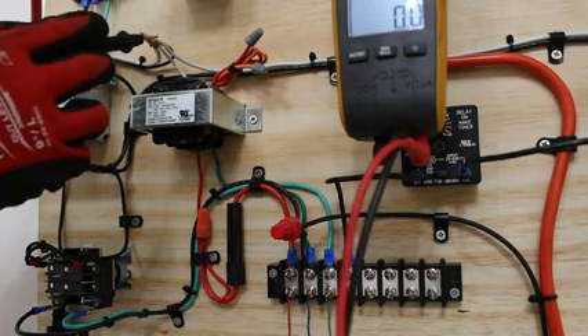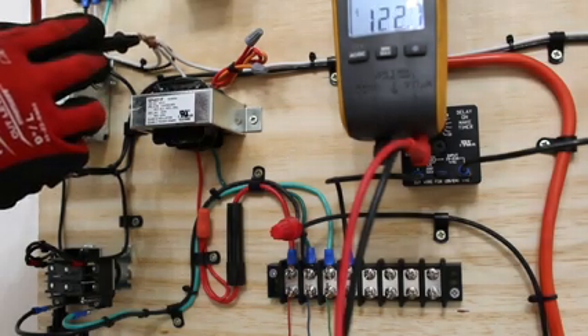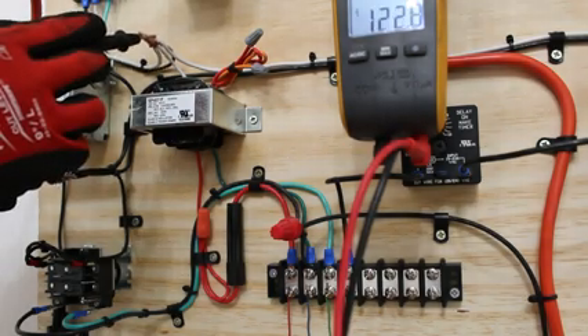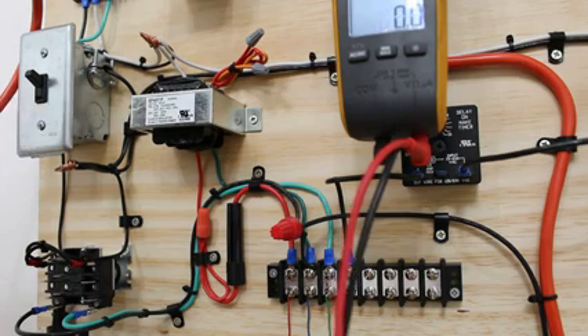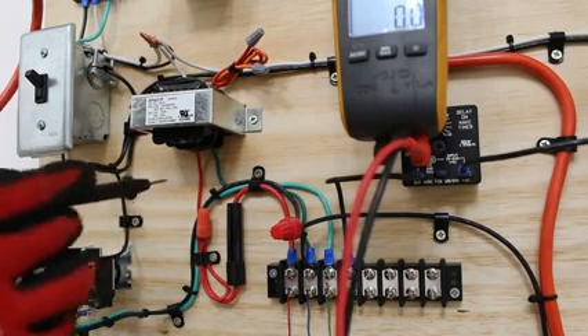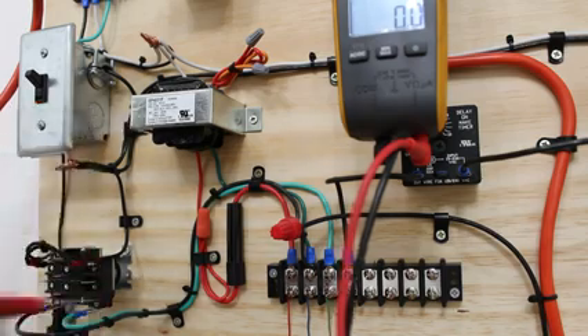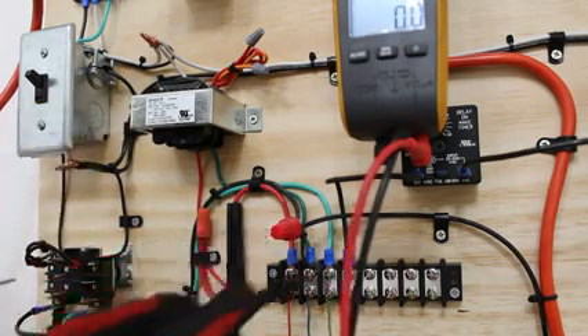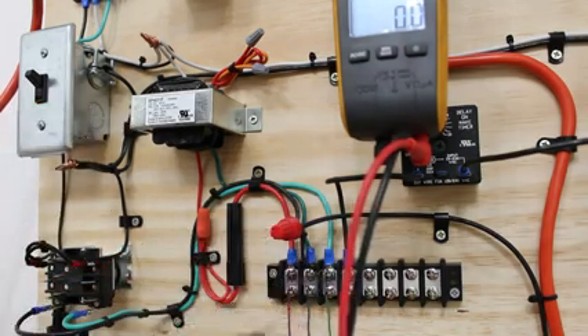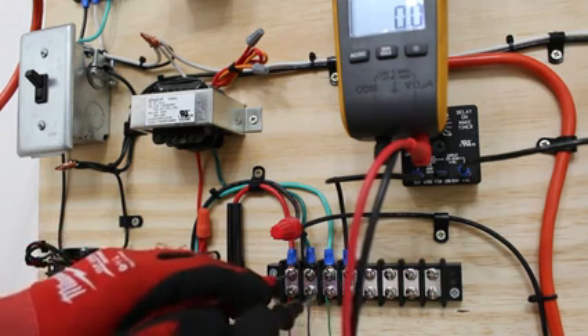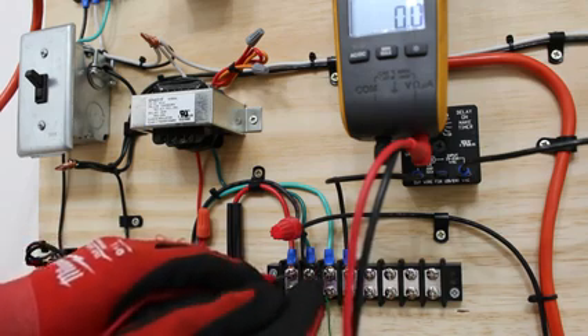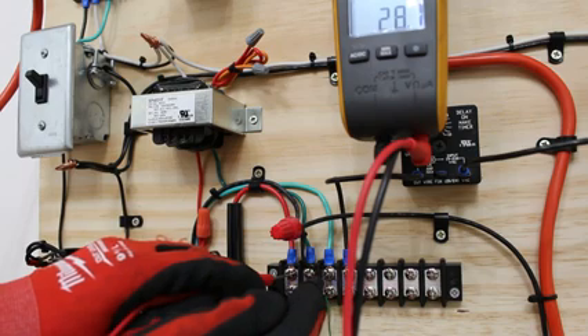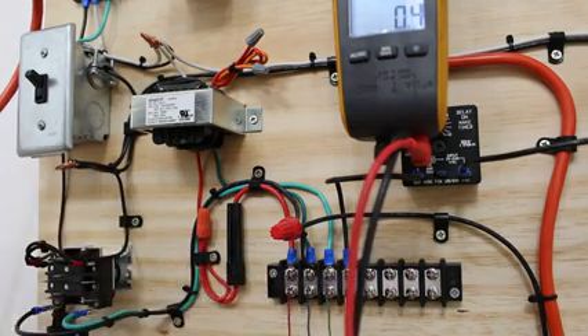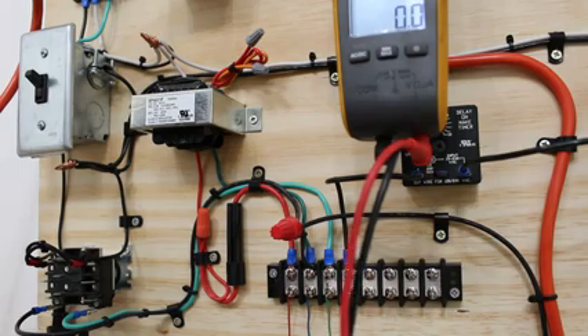So here's our 120, right? We're going to make sure that we have our primary voltage, and then we're going to make sure we have our secondary. You can follow the wires. So it's going to be your red and green, and I can see the red comes here and the green comes here. This is a low voltage terminal block. So between the red and the green wire, right there, we have our 28 volts. So that is a good transformer.